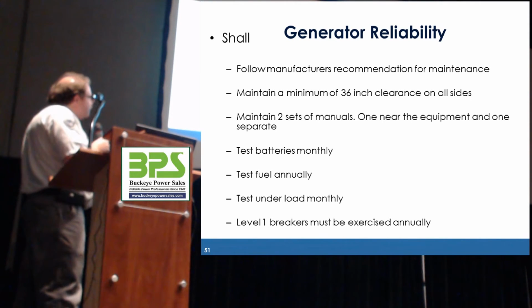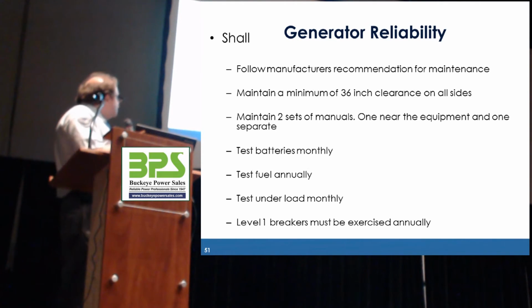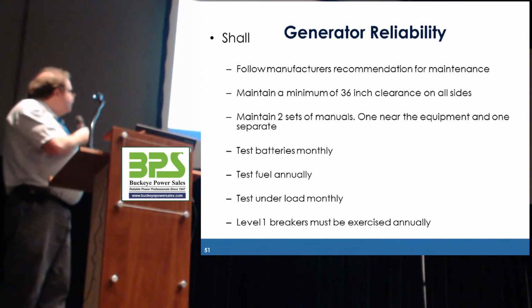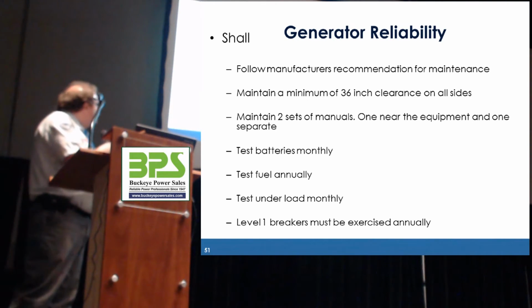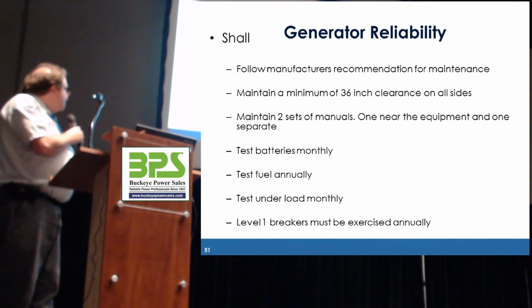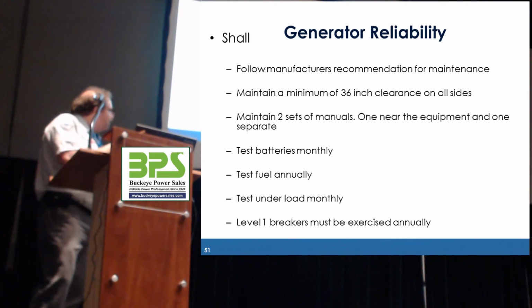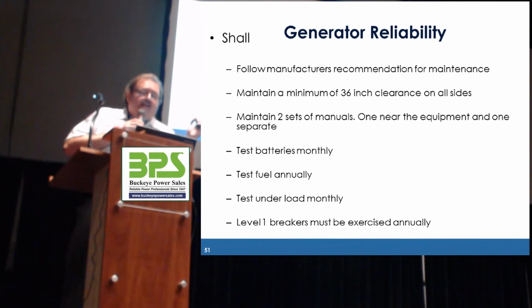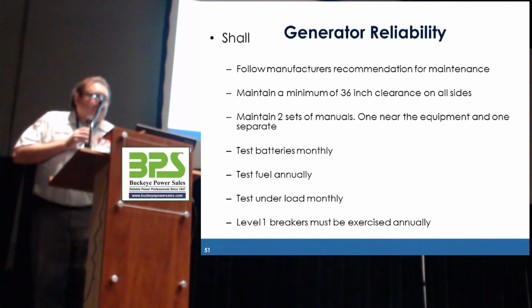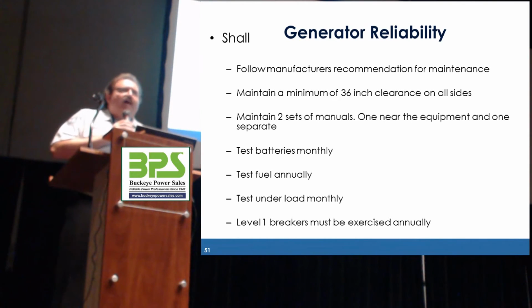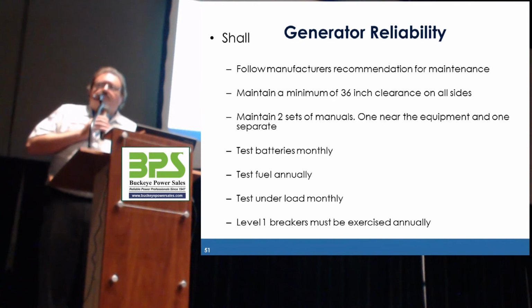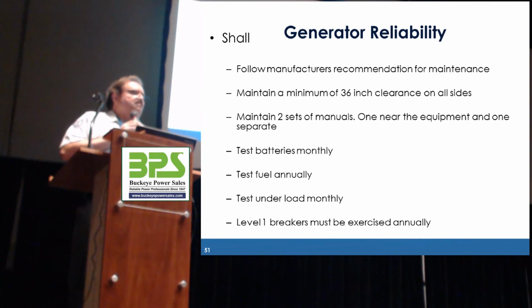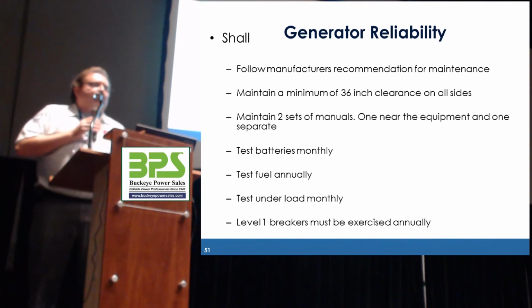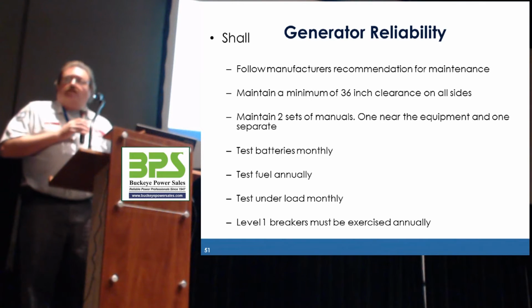You need to have 2 sets of manuals, one near the equipment and one someplace else. The batteries should be tested monthly. Your fuel is checked and tested annually, load bank monthly. And at a level 1 site for life safety, the breakers in the system have to be exercised annually. Because if a breaker just sits and sits and sits and never gets exercised, if it's tripped, there's no guarantee it's going to reclose.